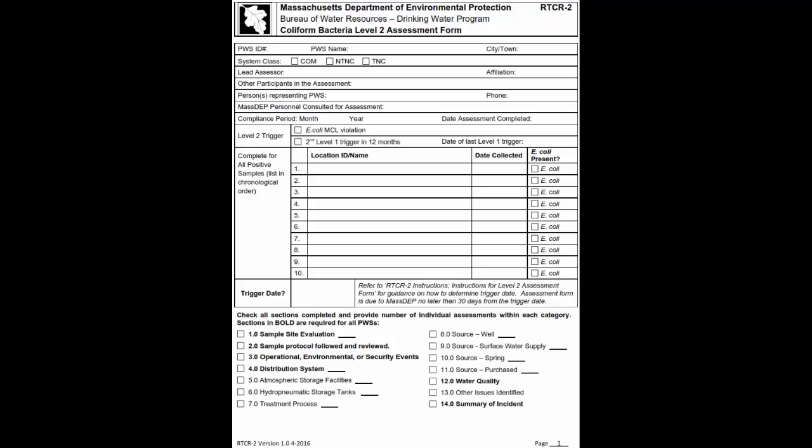That, it's operational and maintenance issues. Has there been a firefighting event or a flushing operation or a sheared hydrant? As a water department, do you have someone in your fire department that routinely calls you if they have a large event to let you know that they're using your water? You may have a change in flow in your distribution system due to a fire issue. And do you have a system of logging those things down? I had a system one time call me and said, anything unusual in your system lately? Nope.